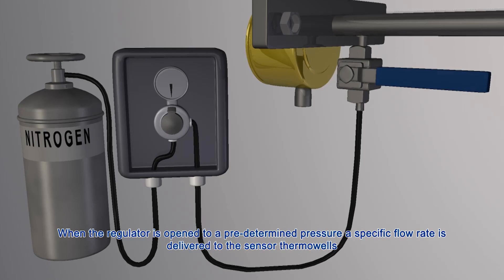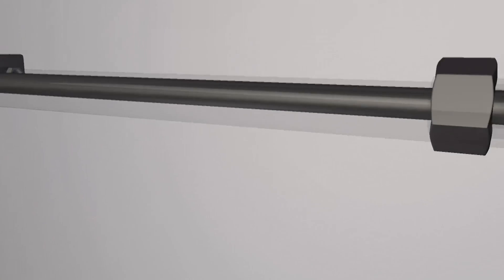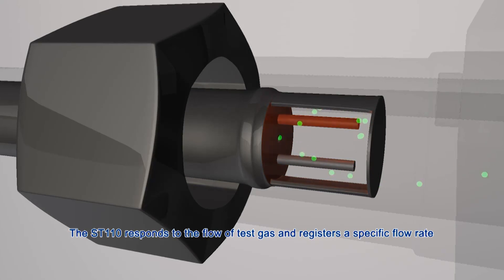When the regulator is open to a predetermined pressure, a specific flow rate is delivered to the sensor thermowells through a sonic nozzle. The ST110 responds to the flow of test gas and registers a specific flow rate.